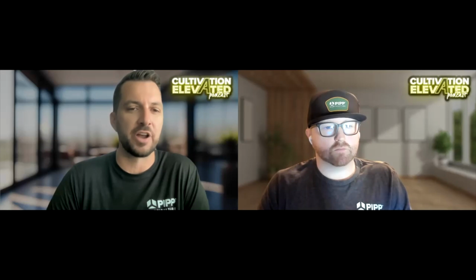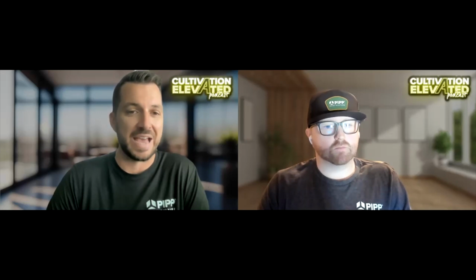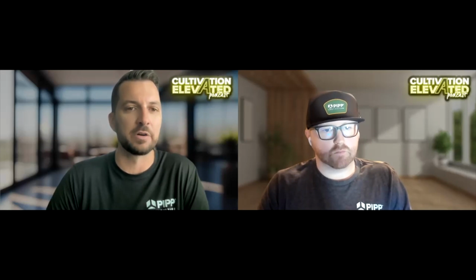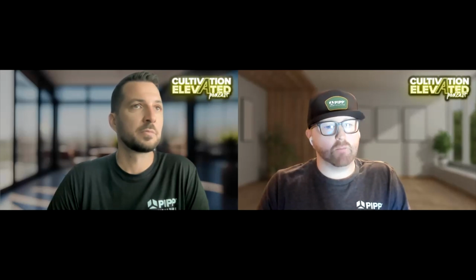When I talk to people about measuring airflow and they bring out a device, 90% of the time it's a vane anemometer. That is because it's the most easily available one, and it's easy to get your head around how it works. When you go on Amazon and look for airflow sensor, you're going to see vane anemometers. Oftentimes they're used by weathermen and by hunters, for ballistic calculators for shooting. They're used for a whole number of reasons outdoors on top of a hill where you're getting mile per hour readings. That's just too much for a lot of what we're doing.